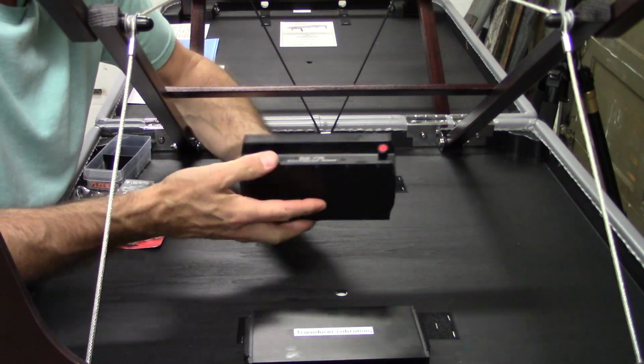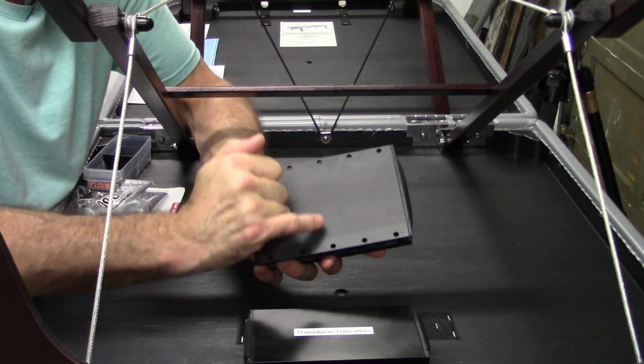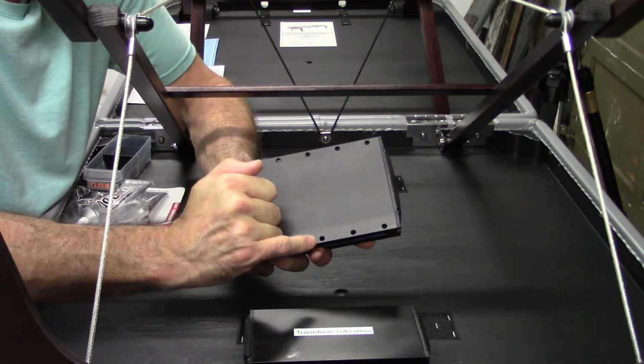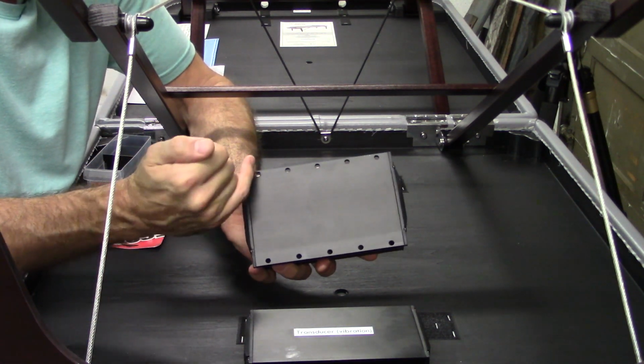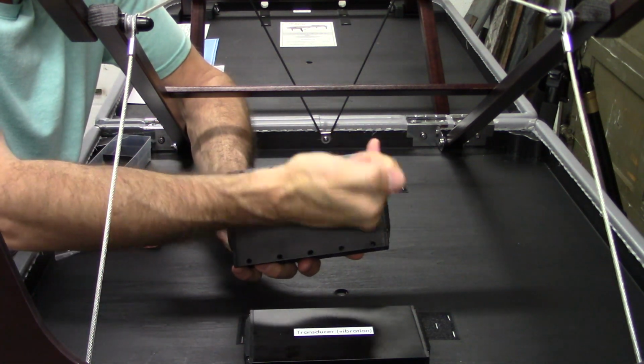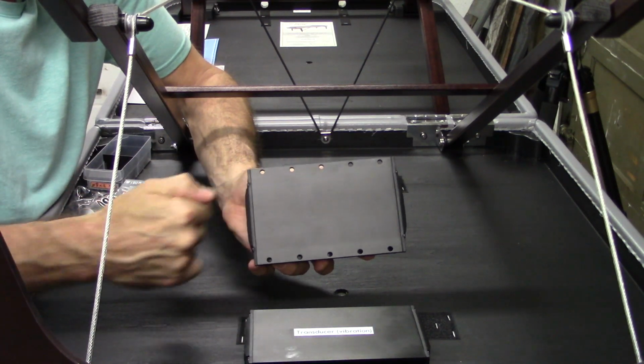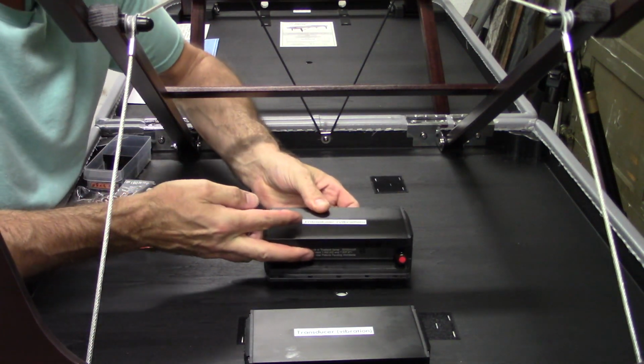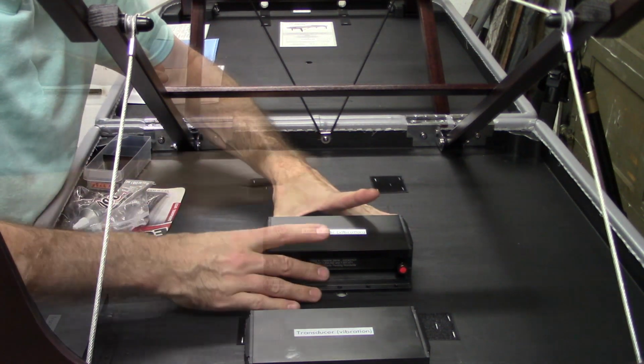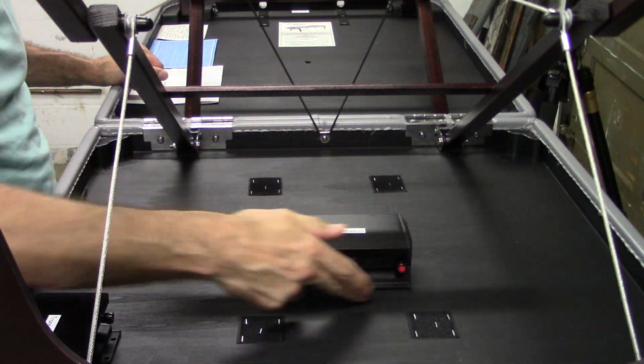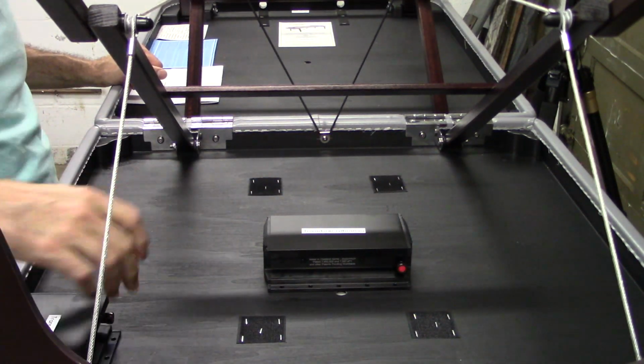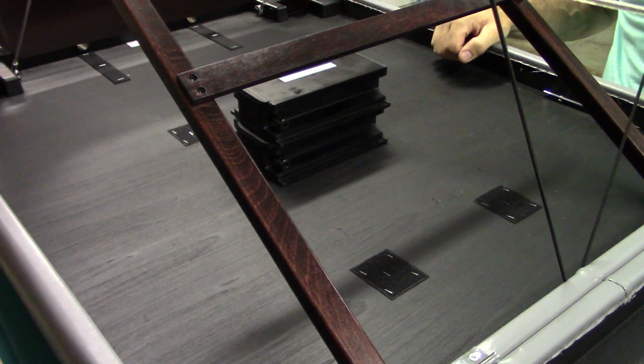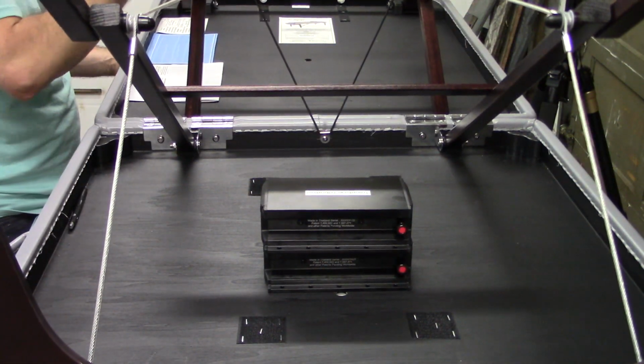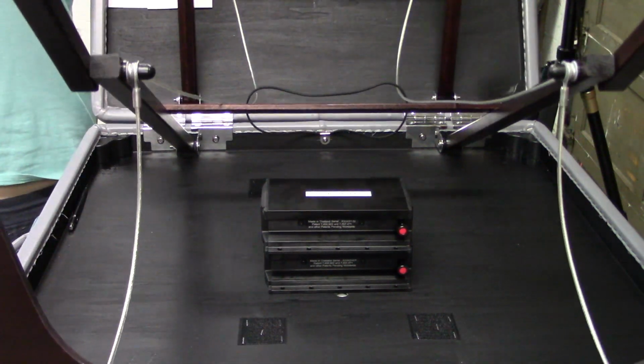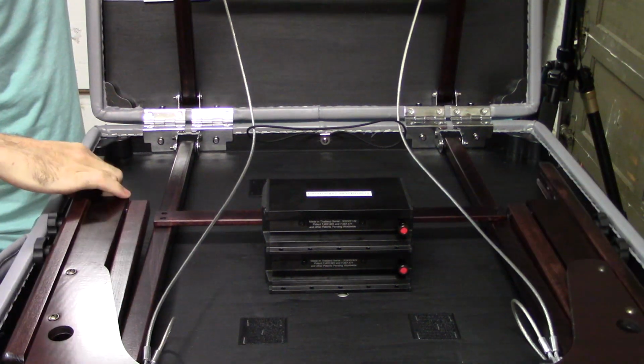So I fortunately have a little drill hole on either side of this, which tells me the center. 1, 2, 3, 4, 5. That means the one in the middle, number 3, is the center point. Once we find out what the center line is and you've marked this off, you're going to place the second transducer right on top of it. You're then going to close your table up again. And this time, you're going to close it all the way.